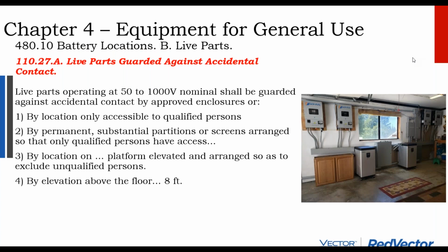The main thing is live parts operating at 50 to 1,000 volts nominal. And this is squarely within the realm of home battery banks, and even lead acid has 48 volt nominal. In the lithium ion industry, we'll refer to a 48 volt battery bank as a 48 volt battery bank. But if you open up the spec sheet, you'll see that its resting voltage is closer to 50 volts. Our 48 volt batteries on the spec sheet are read as 51 volts nominal. Live parts operating at 50 volts to 1,000 volts nominal shall be guarded against accidental contact by approved enclosures.